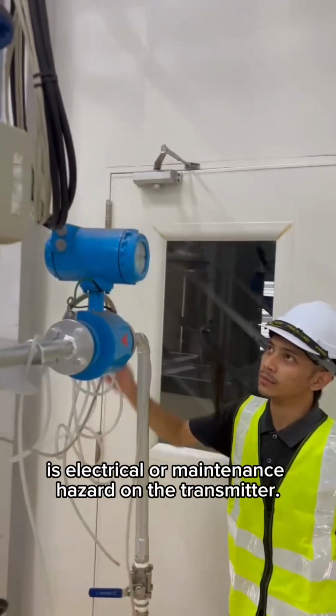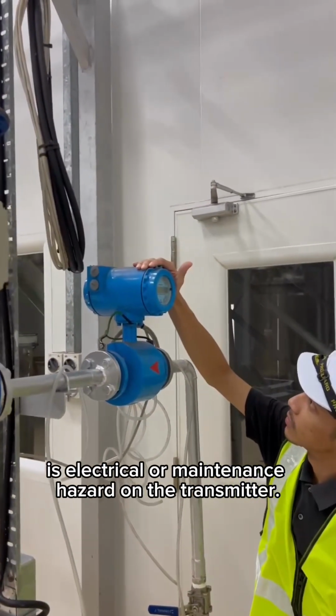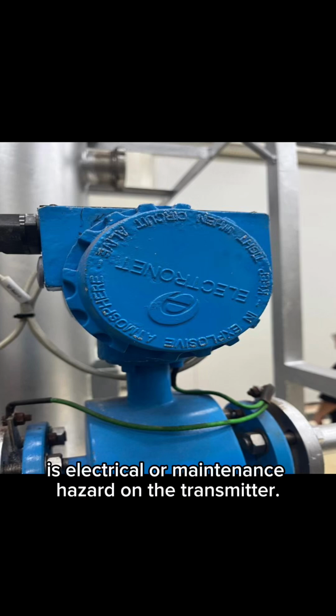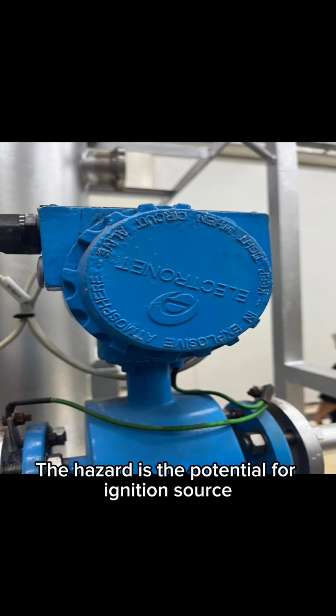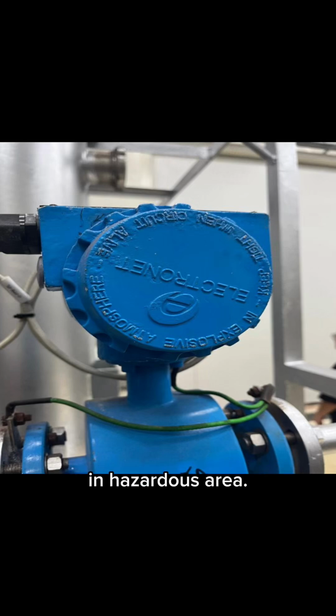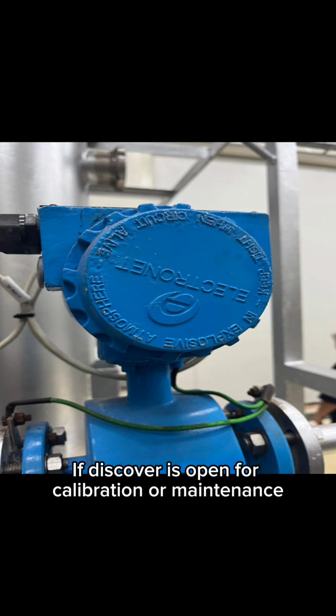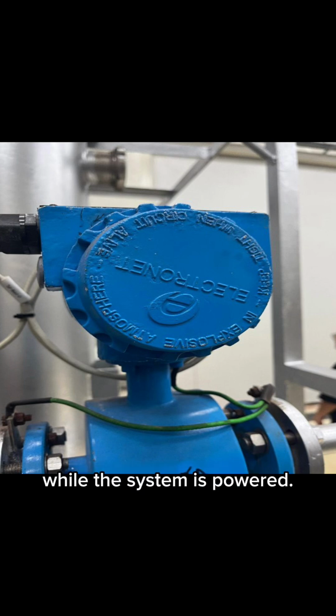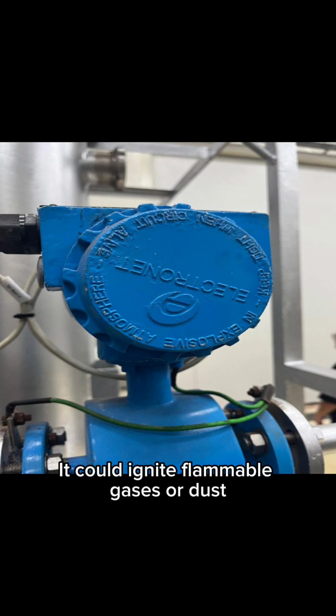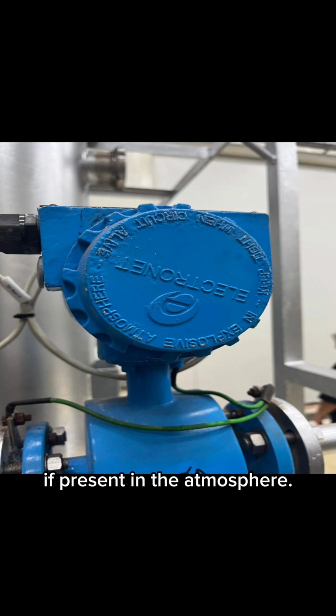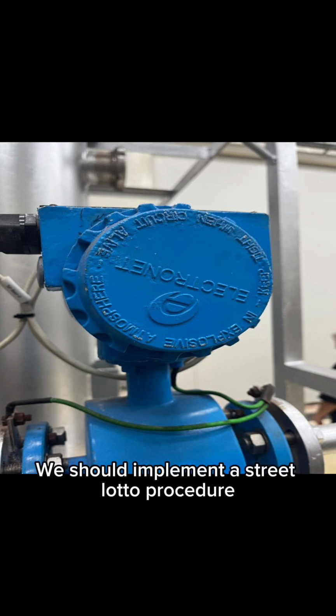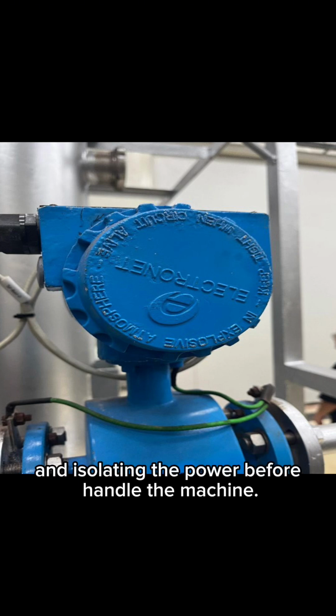Firstly, there is an electrical or maintenance hazard on the transmitter. The hazard is the potential for an ignition source in a hazardous area. If this cover is open for calibration or maintenance while the system is powered, it could ignite flammable gases or dust if present in the atmosphere. We should implement a strict LOTO procedure and isolate the power before handling the machine.